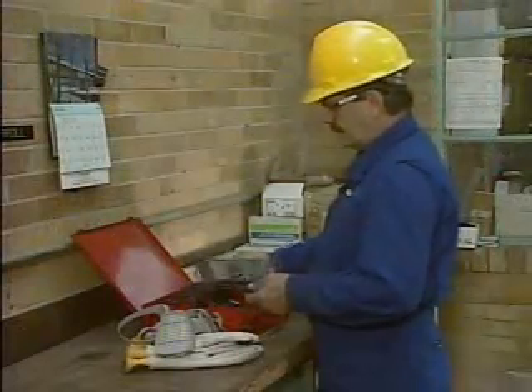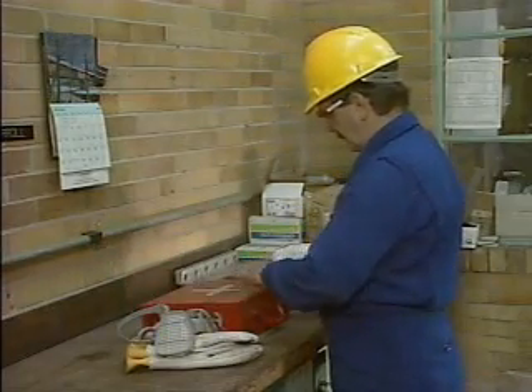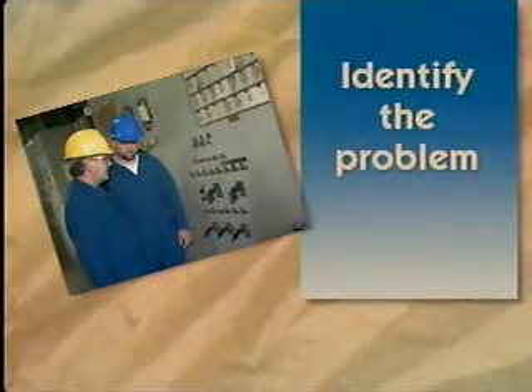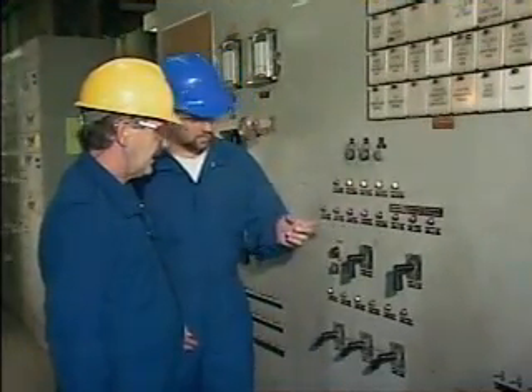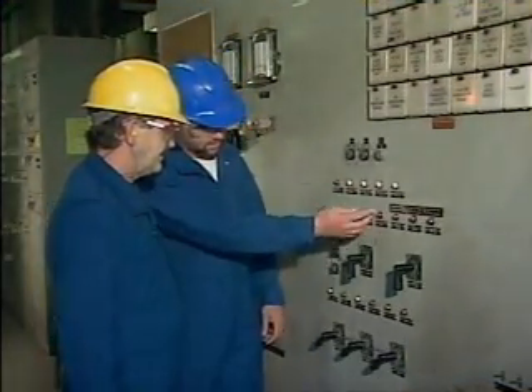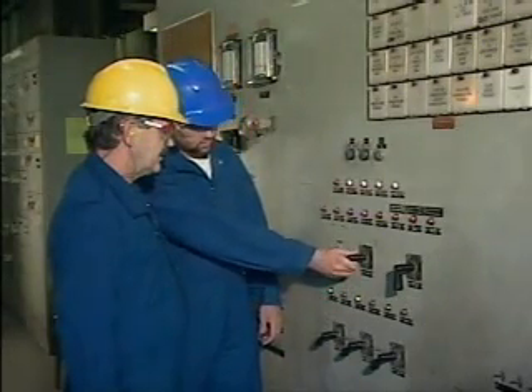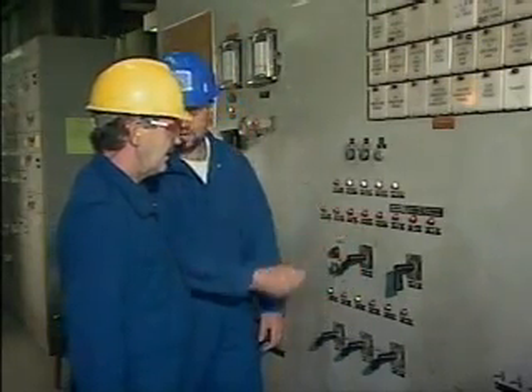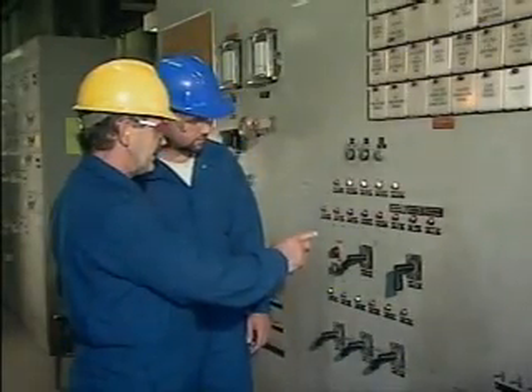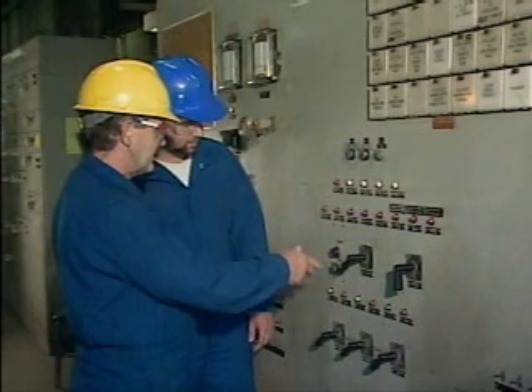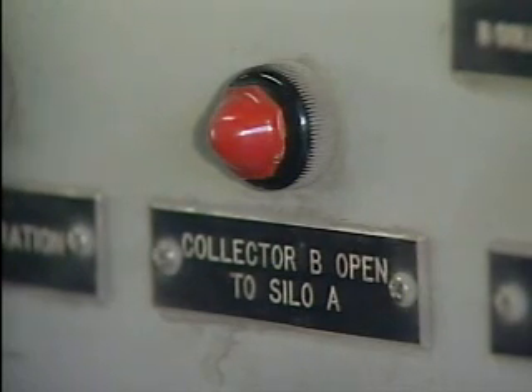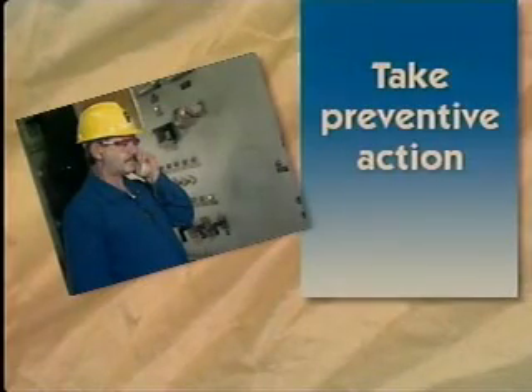The electrician uses it to get more information about the problem. He gathers the tools, test instruments, and safety gear that he'll need for this job. To take the first step in troubleshooting this problem, the electrician talks with the operator who reported the problem. At the process's control panel, the operator repeats the startup procedure that he tried when he attempted to route the fly ash in the process's B collector to the process's A silo. As they attempt the startup procedure again, the electrician sees for himself that the process does not operate. After the electrician has identified the problem, he takes steps to prevent unnecessary downtime, damage to plant equipment, and injury to plant personnel.